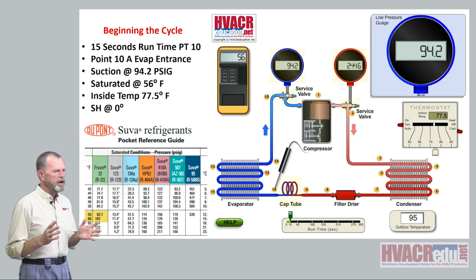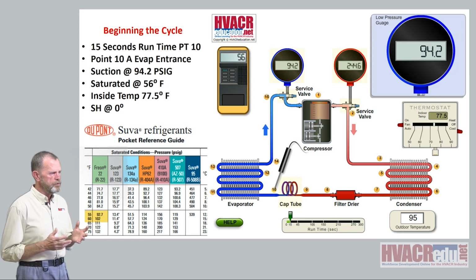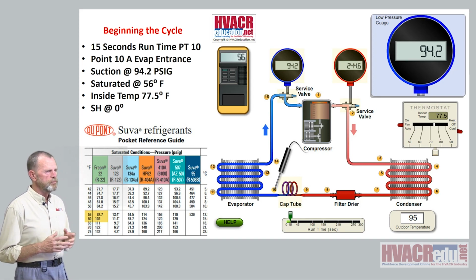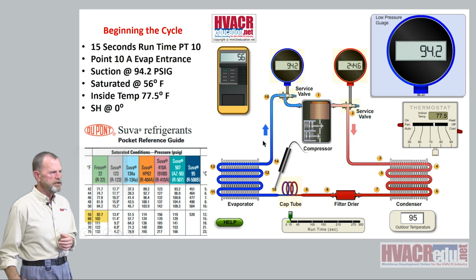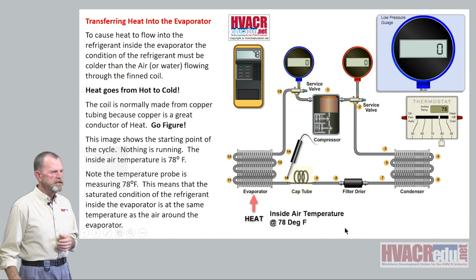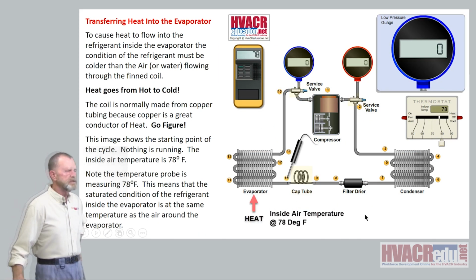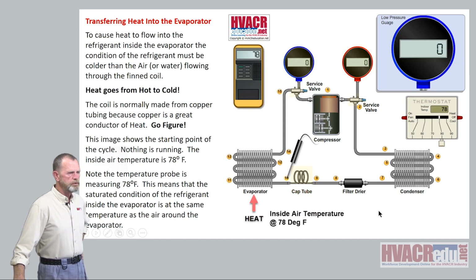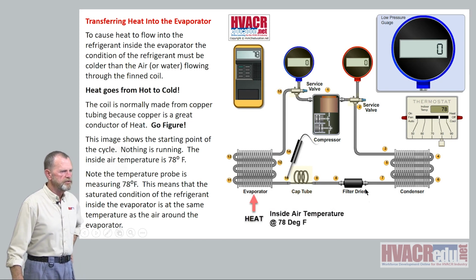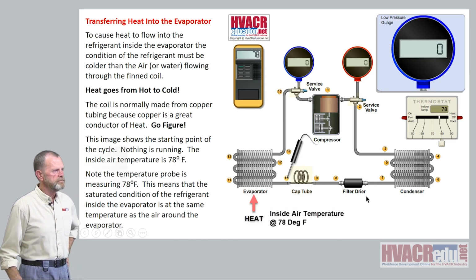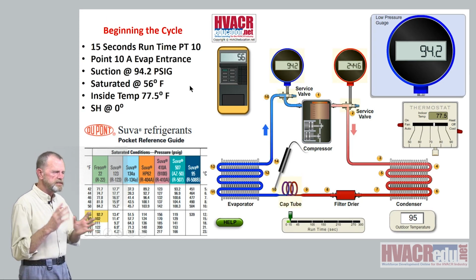All right? And what happens when you just start a cooling system? If you remember, the temperature in the previous slide was 78 degrees, the air coming into this thing right there, 78 degrees inside air temperature. All right? So that's where we're starting. Notice the thermostat says 78 degrees as well. The temperature probe says 78 degrees. So everything was static at 78 degrees. So we're just started. And that's important to know.